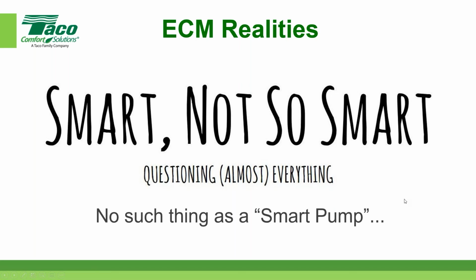I spend a lot of time doing engineer lunch and learns on our bigger pumps, and one of the things I'm constantly trying to get the engineers to do is put the actual mode of operation that they want within the circulator notes. Out on the right hand side of a circulator or pump schedule, on the far right, you have the notes that tell you what we want to happen, some general statements. They have the flow and the head and an operating point, all that stuff, but they've got a place for notes. And more importantly than anything, what we want there is for them to tell the person doing the commissioning or the startup what mode of operation they designed the system for.